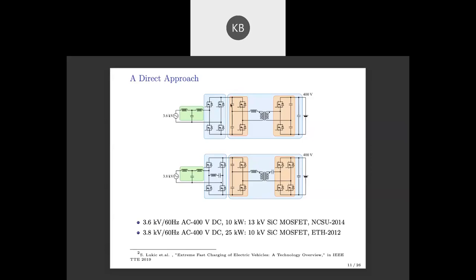Then you have a bridge that converts this 7 kV DC to a 20 kilohertz high frequency AC, which passes through the transformer, and the other side bridge rectifies it. The voltage is stepped down by this medium frequency transformer, and then rectified, becoming 400 volt DC on this side.